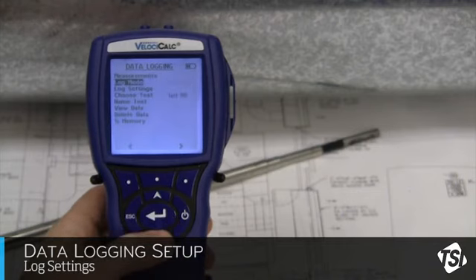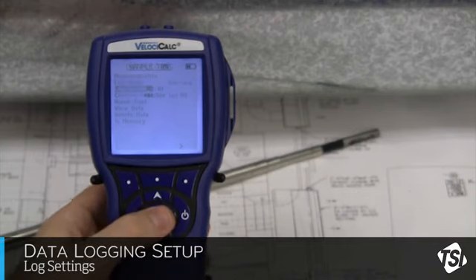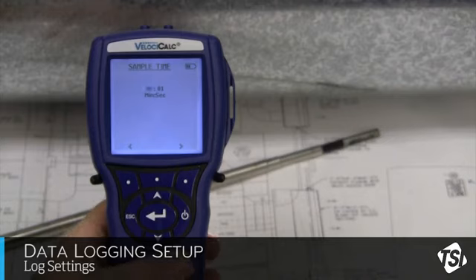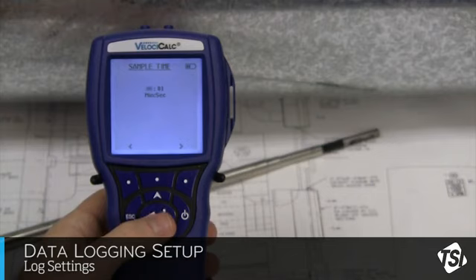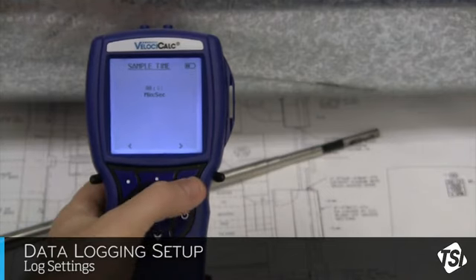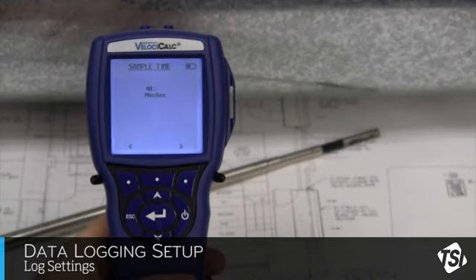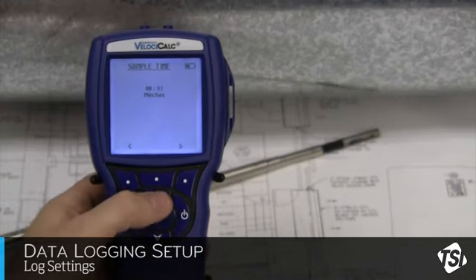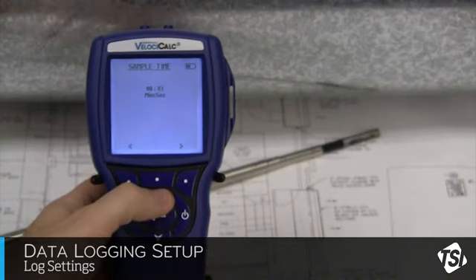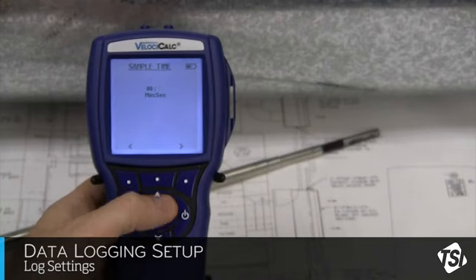We need to select the sample time. This is how long the unit will take a reading at any given point and in the end log the average for that reading. If you have turbulent airflow, having a longer sample time can help to average it out. In my case, I will choose 10 seconds. But just know that this may need to be adjusted according to your specific conditions.